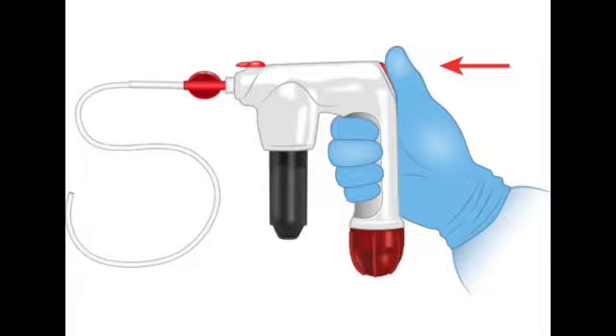Visibility is rapidly deteriorating. But if the doctor accidentally taps that suction button, the negative pressure will instantly pull ambient fluid directly into the tip of the Hemospray catheter. And the moment that happens, the powder inside the tip instantly cross-links and forms a concrete plug. The procedure is instantly compromised, so the endoscopist has to actively fight their own reflexes. They must deliberately shut off their primary tool for visibility. Just let the blood pool and rely entirely on that continuous manual flush of dry air to keep the tip clear as they hover into position. Right. Assuming they navigate that minefield perfectly, of course. Okay, so let's say they do. The scope is dry. The catheter has advanced down the channel, shielded by a continuous blast of air.